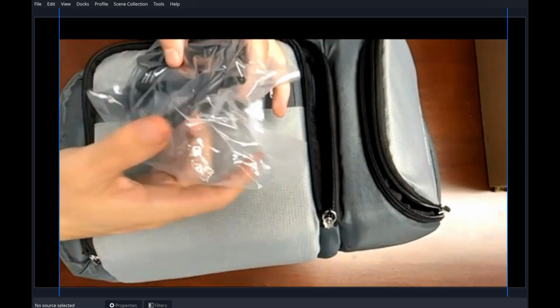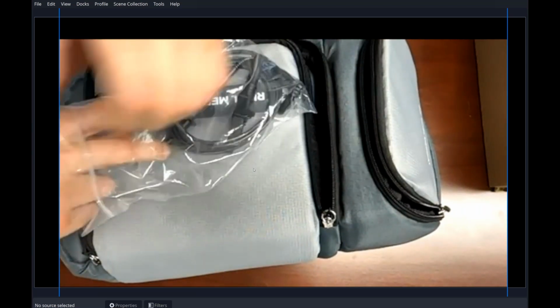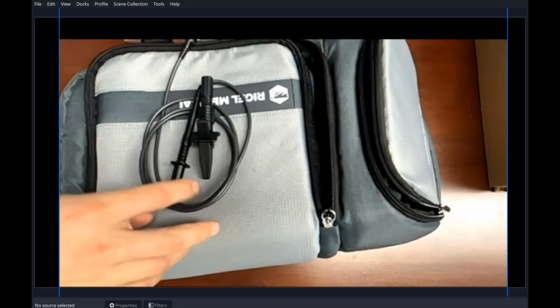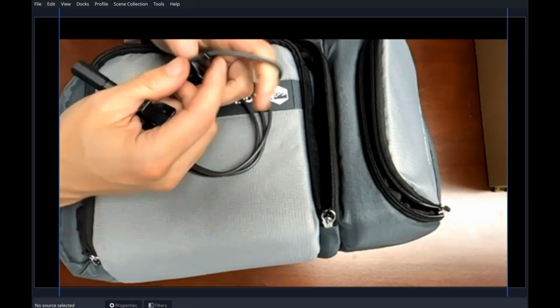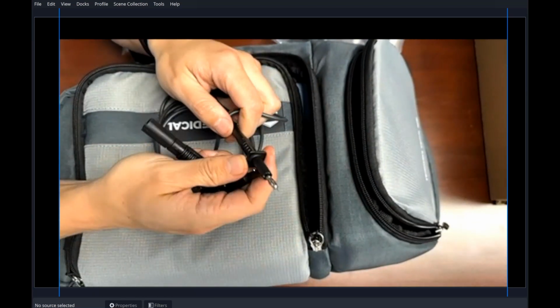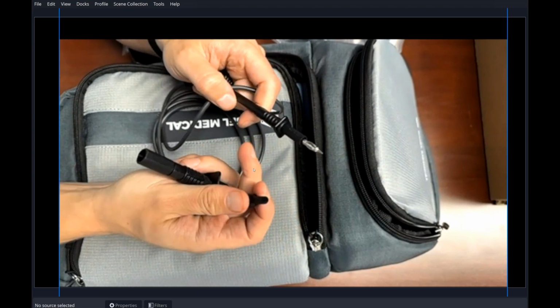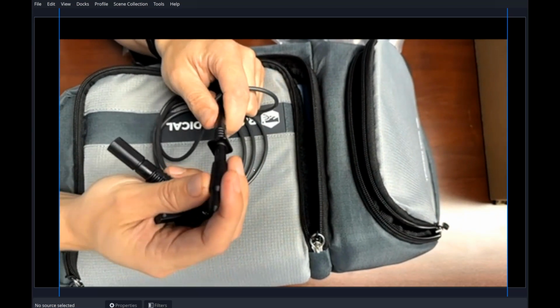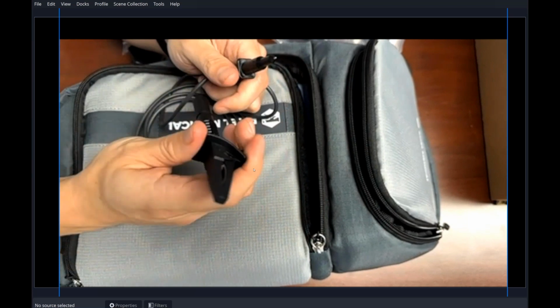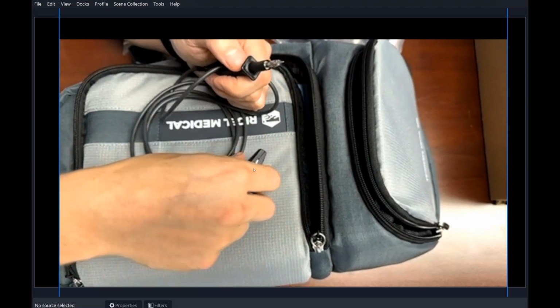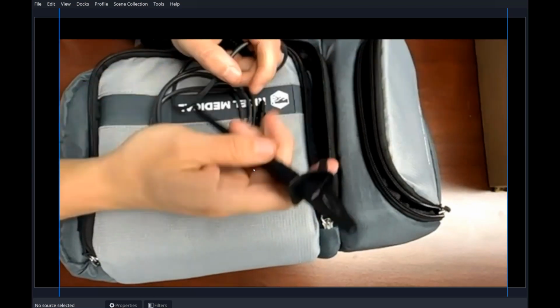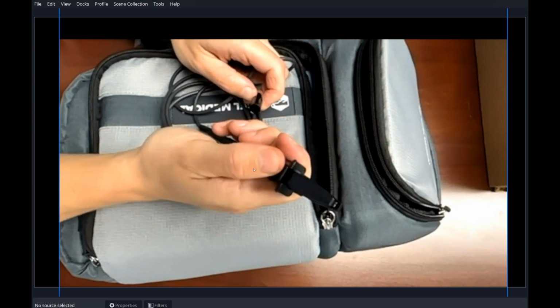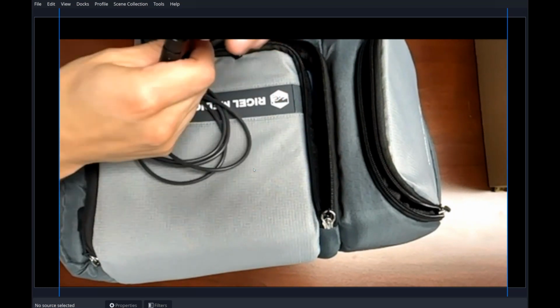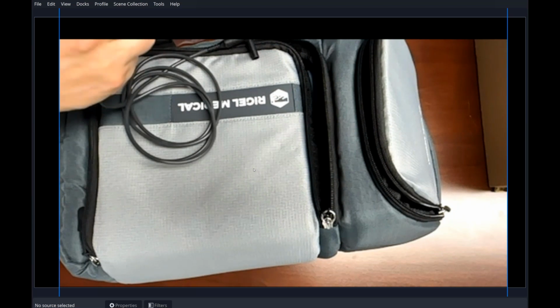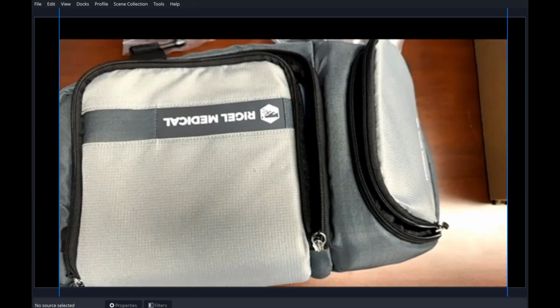And then there's another Earth bond lead. It comes with a crocodile clip, but it has this option to connect directly to the medical device for any exposed conductive parts, which the alligator clip just can't reach. You can attach this and then have that as a crocodile clip style solution as well. So that's the bag. I'll just get the analyzer out.